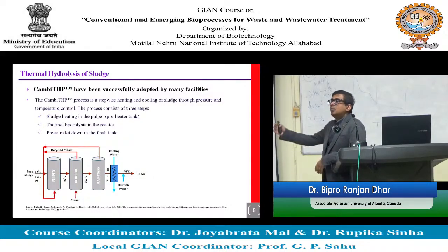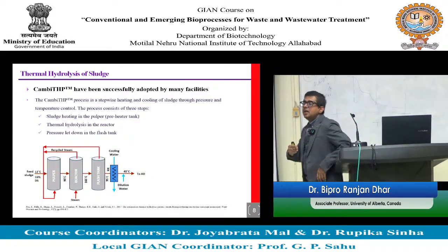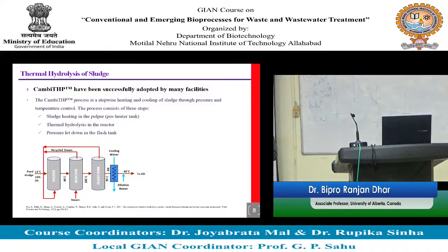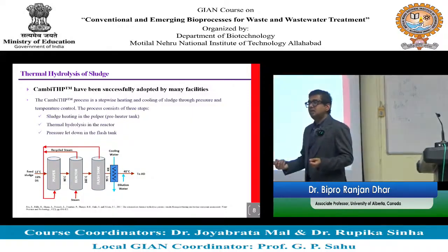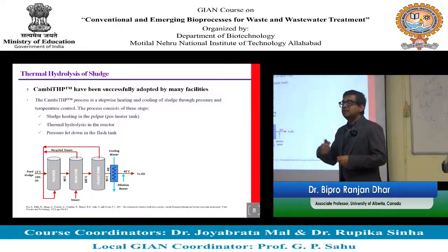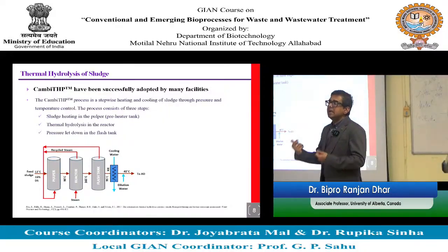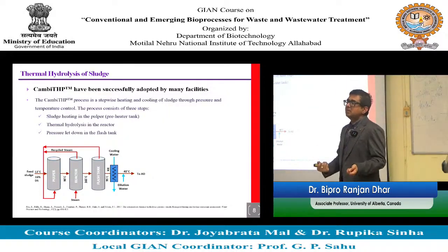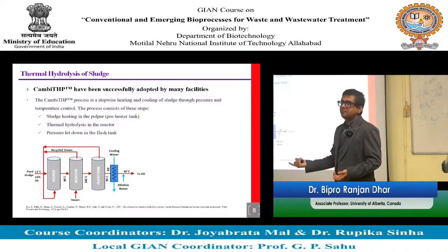So you are reducing the solid residence time by almost 50%. So a 50% reduction in solid residence time means you can treat double, basically enhancing the capacity of your existing facility by 50% or 100%, right, if you double.